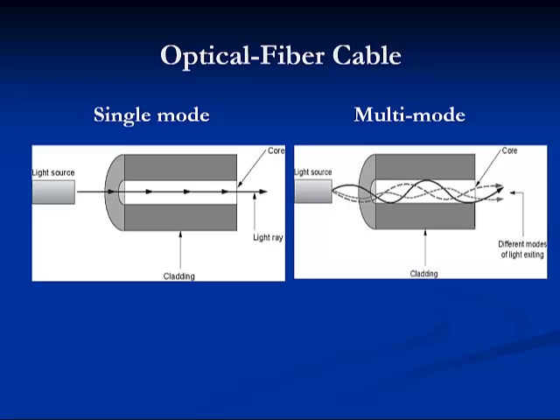With single mode optical fiber, a fabricated laser which transmits a single coherent light pulse is used. Multi-mode fiber is an optical waveguide in which light travels in multiple modes or rays. Typical multi-mode core size is larger than single mode and comes in either 62.5 micron or 50 micron core diameter. Light rays enter the core at various angles in multi-mode fiber because the multi-mode light pulses are generated by an LED laser power source, and it's not nearly as coherent as single mode.